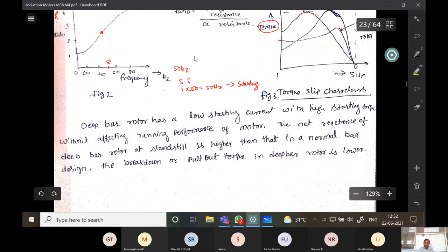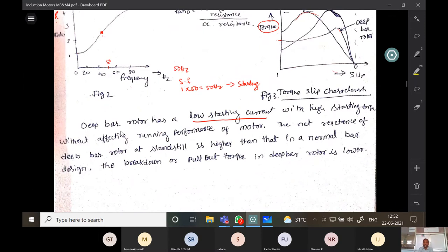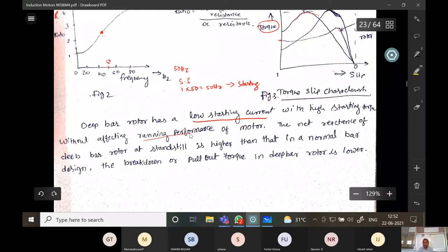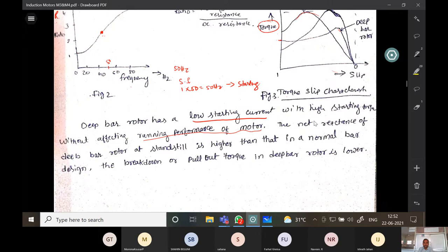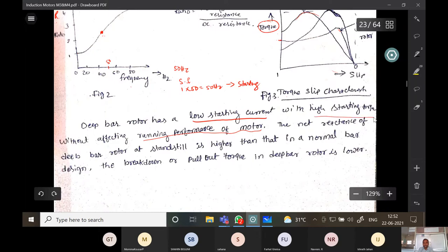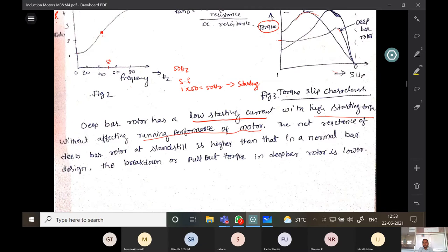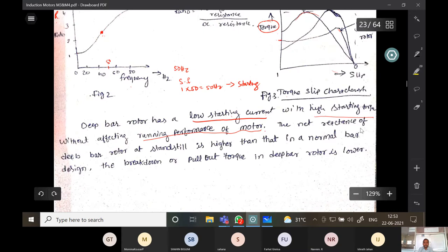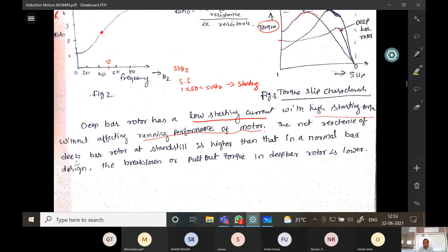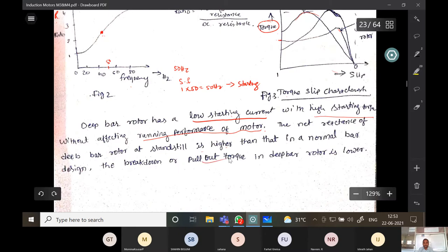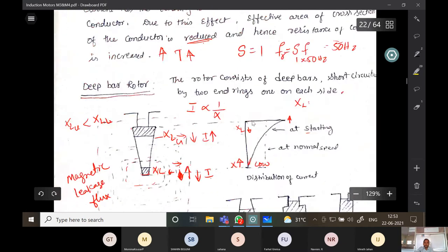The deep bar rotor achieves high starting torque without affecting the running performance of the rotor. However, the net reactance at standstill is higher than the normal bar design, so the breakdown or pull-out torque in the deep bar rotor is very much lower. This is about the deep bar rotor.